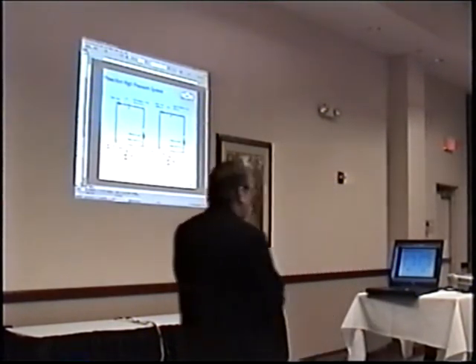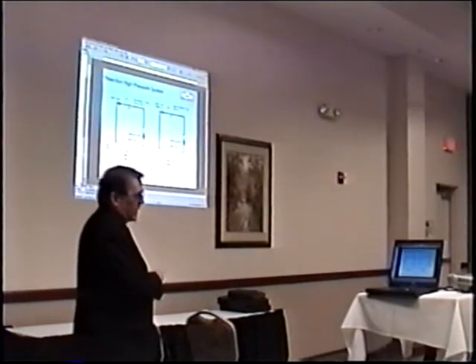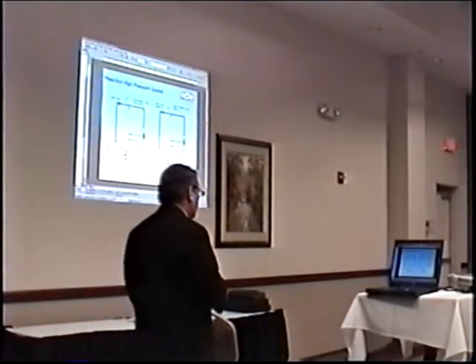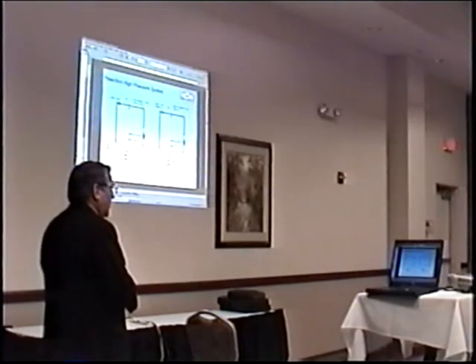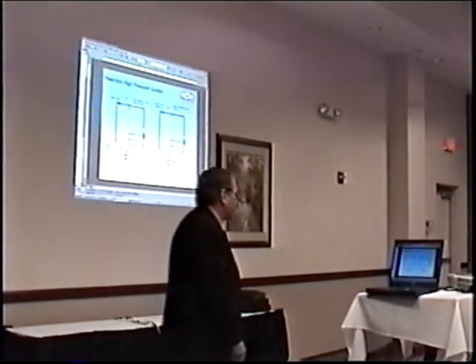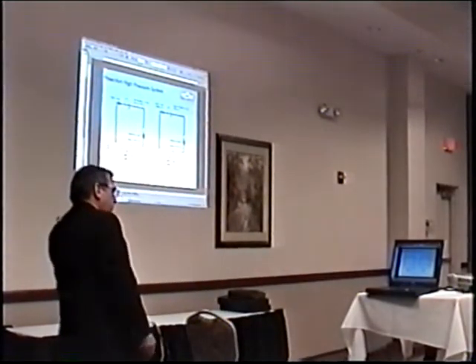The systems have volumes that are quite small, like 100 liters. The other systems are more like 200 liters, the larger systems. But now the pumps deliver, if one motor starts, basically 100 liters per minute. Theoretically, it would take the first motor a minute to put 100 liters out to fill the pipe.